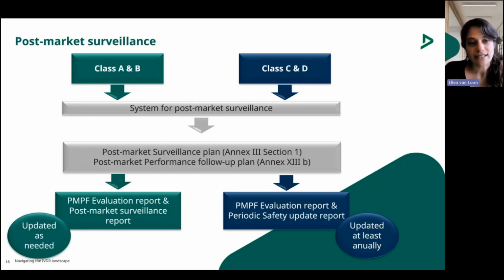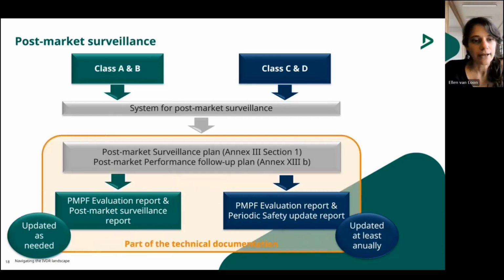Also good to realize is that this periodic safety update report for Class D devices is also being sent to the notified body. So all the plans and the reports are actually part of the technical documentation. We have a next webinar planned where we will go more into detail on the post-market surveillance system in the IVDR.